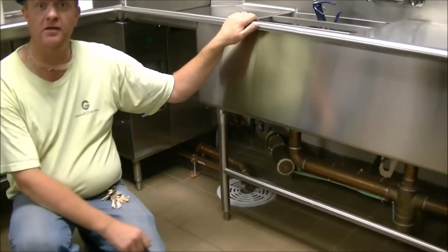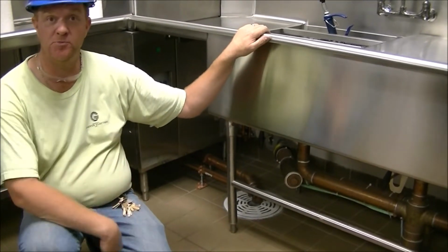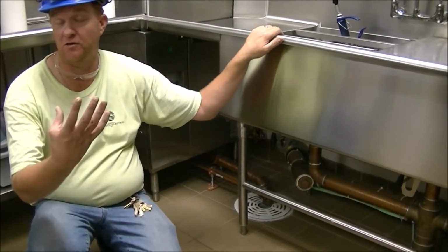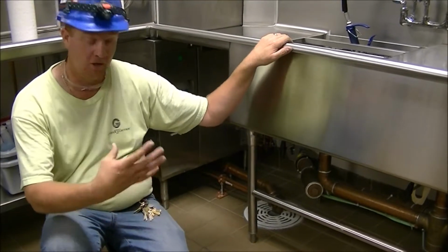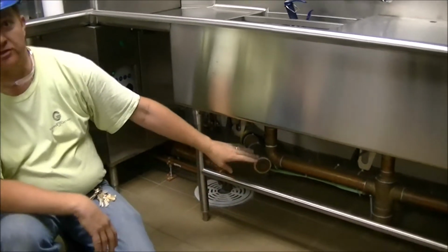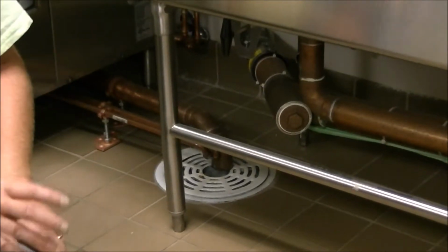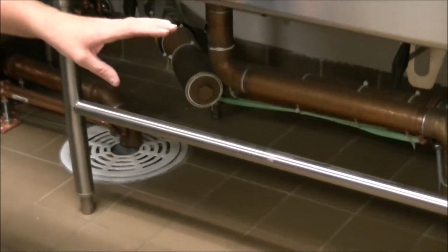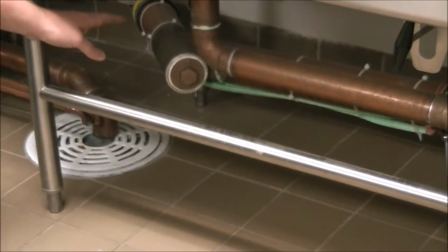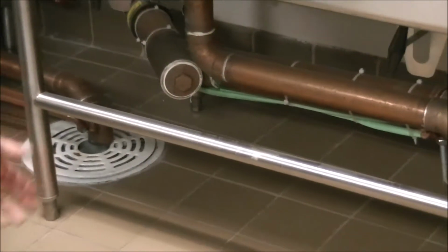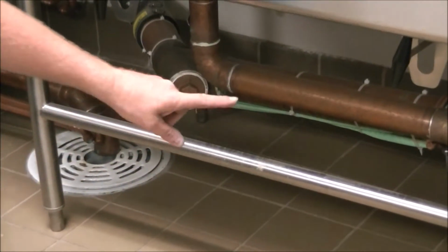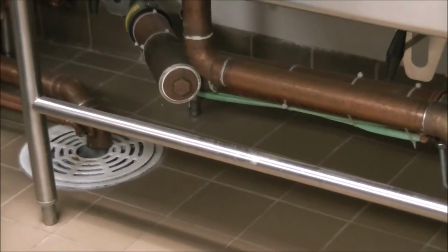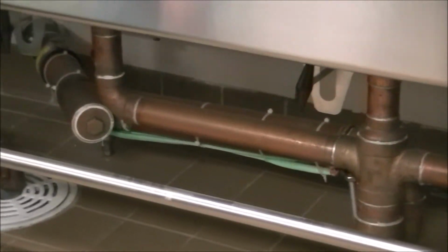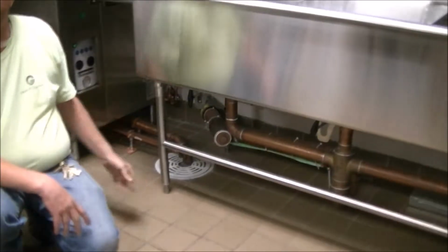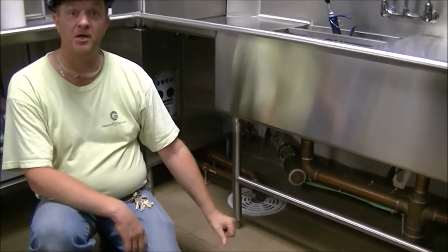The heat trace is basically a heating cable we just put power on the end of, and it warms up. It doesn't get particularly hot, but we're using it. It's usually used to stop pipes from freezing, but here we're using it to keep the flow of grease moving, so if grease goes down the sink traps it washes away and doesn't clog anything up. It's attached to the pipes underneath here, goes behind this wall and is attached to all the pipes back there, then down into the basement dumpster area.